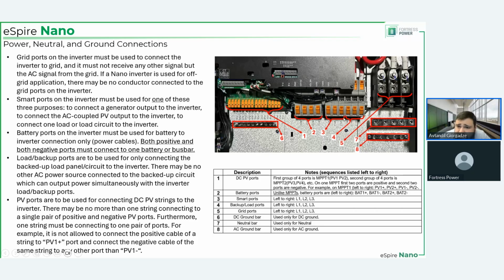Number 4, these are L1, L2, and L3 for backup loads. This is your backup ports. These are the ports that provide backup for your site in the case of a grid outage. These are also the ports that you use if this is an off-grid application to output the power from the inverter to the loads.